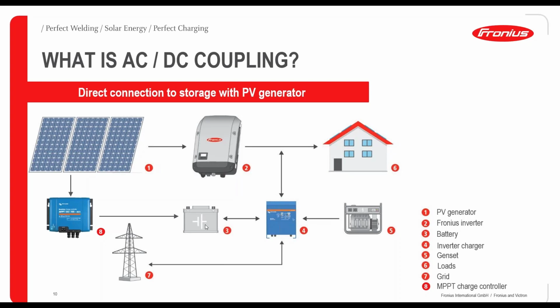What is the big advantage here? You again have high efficiency at daytimes when PV power is generated, because you can directly supply your loads and directly recharge your battery - you don't necessarily need the genset, since you have the direct connection to the battery. The inverter charger controls all three components - battery, grid, and generator - and builds up the grid, so you have it again as a core element.